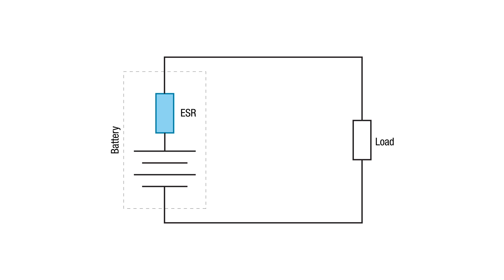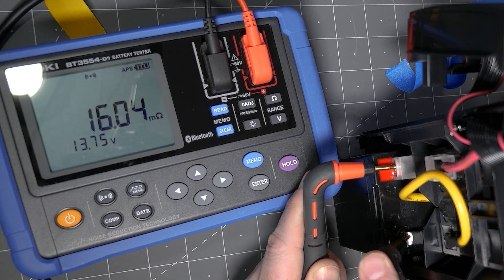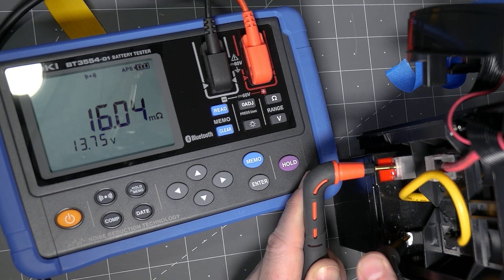Just like a real resistor, ESR drops some voltage and wastes energy in the form of heat. As the battery charges, discharges, and ages, that resistance goes up. Eventually it makes the battery unusable. By measuring the ESR, the Hioki meter can quickly tell us something about the health of a battery while it is in operation.